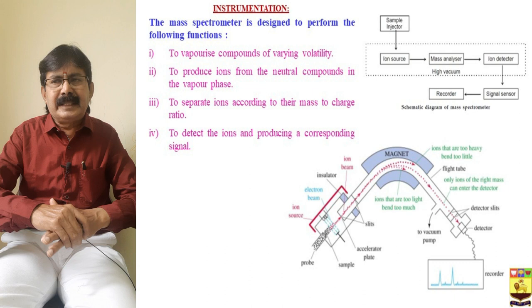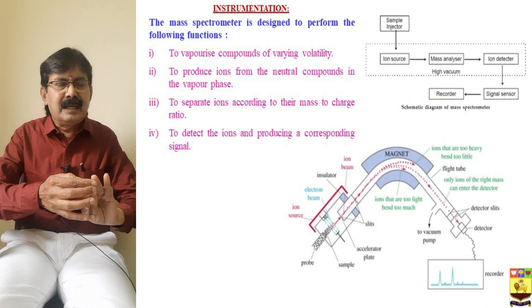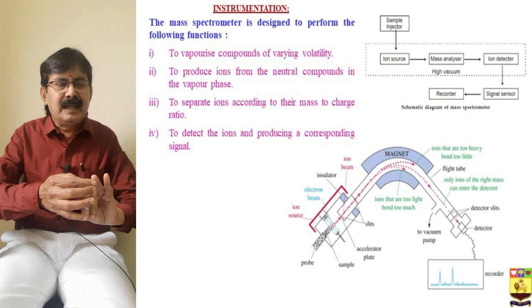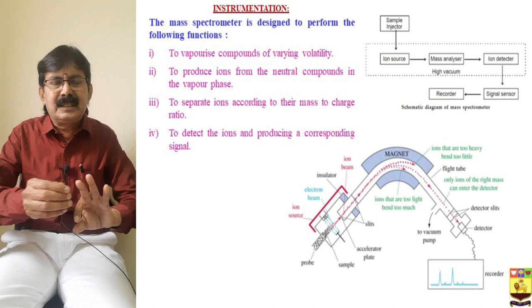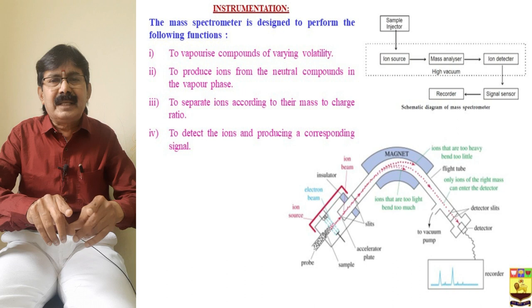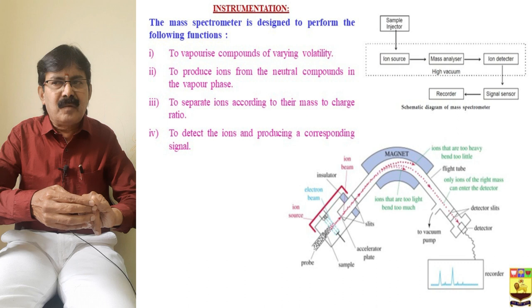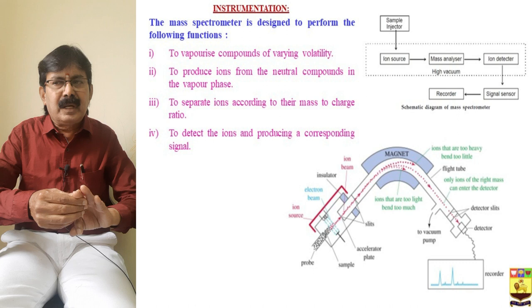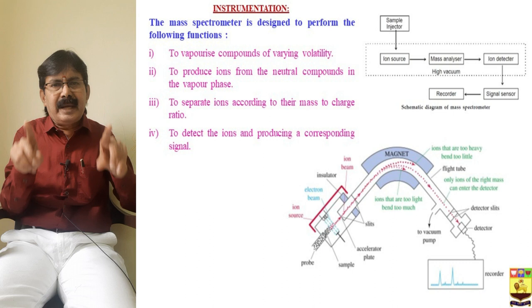The mass spectrometer is designed to perform the following functions: first, the sample injector; then the ion source; and the mass analyzer cell, which is at high vacuum; followed by the ion detector, amplifier, and recorder. The first function is to vaporize compounds of varying volatility and to produce ions from neutral compounds in the vapor phase, to separate the ions according to their mass-to-charge ratio, and to detect the ions producing corresponding signals.